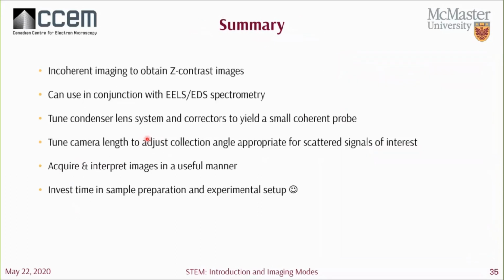All right, so in summary, Z contrast images arise from incoherently scattered electrons, giving us our Z contrast images. We commonly use them in conjunction with EELS or EDS spectroscopy. You can tune the condenser lens system to give you a really small coherent probe. And then you're also going to want to tune the camera length to adjust the collection angle that's appropriate for the scattered signals of interest.